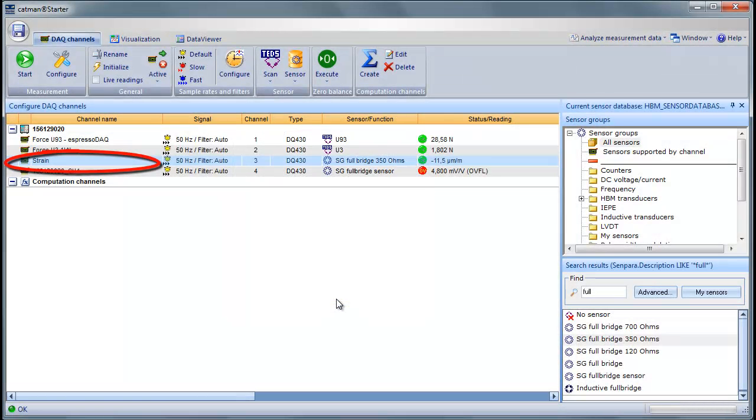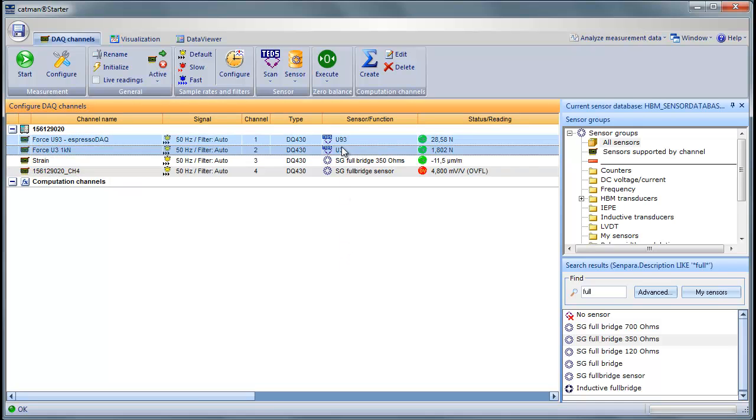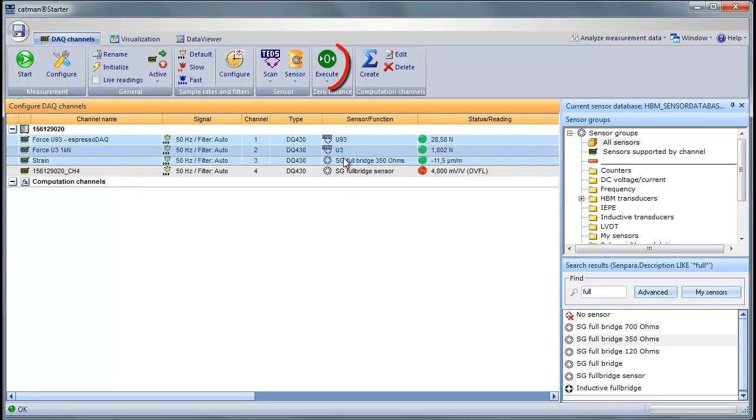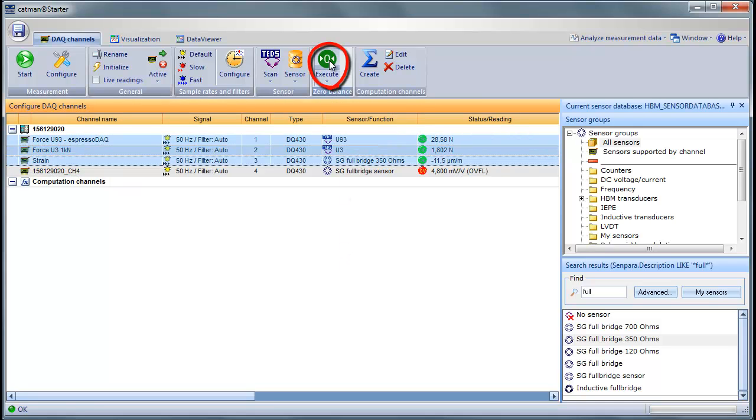Now we'll select all three channels and run a zero balance adjustment. Since we're happy with the standard measurement parameters like sample rate and start-stop conditions, we can start our first data acquisition by pressing the Start button.